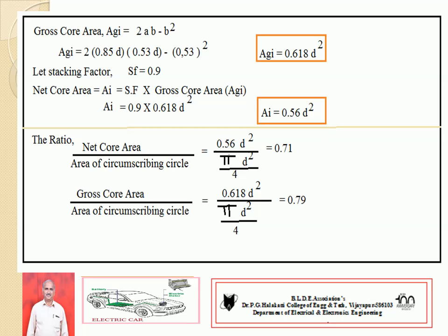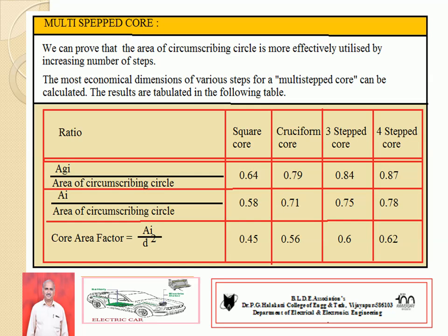The ratio of net core area to area of circumscribing circle for the two-stepped core is 0.71, and gross core area to area of circumscribing circle is 0.79. For multi-stepped cores — where the number of steps used is above two — observe from the table that from an economical point of view and for more utilization of core area, the four-stepped core gives utilization factor of 0.87. The utilization factor of the core increases with stepped cores and multi-stepped cores.